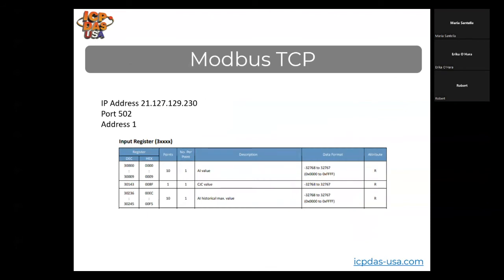So today for the Modbus TCP application demo, I'm going to use these parameters. I have a PLC with a given IP address. Port 502 is the data port, which is pretty much standard for Modbus TCP, and the address is 1. The registers I want to monitor are just 30,000 and 30,001, which are analog input registers. And we're just going to connect that to our SCADA system for monitoring.